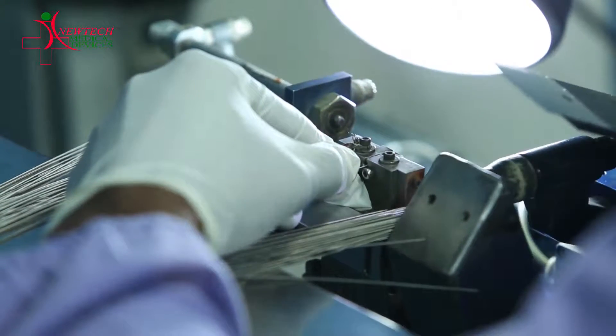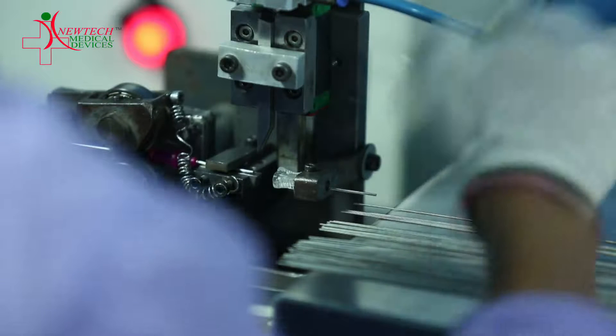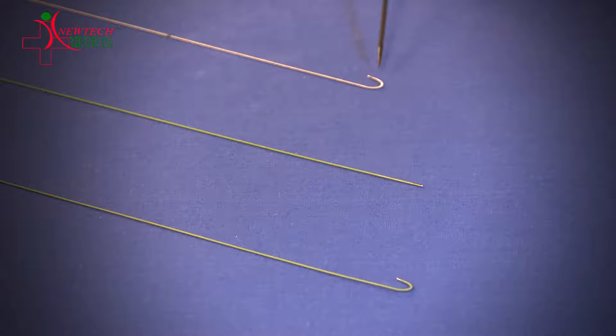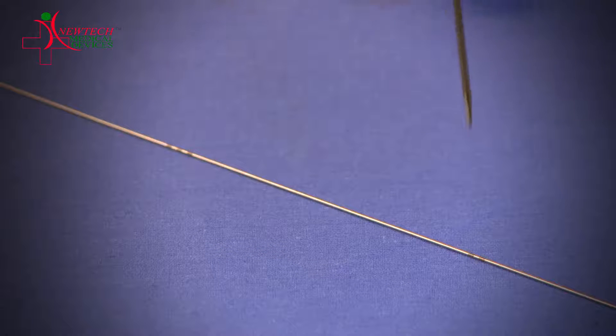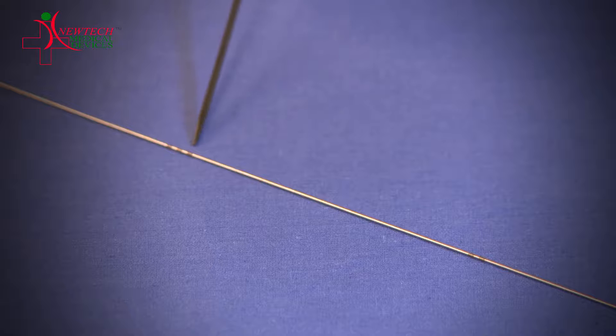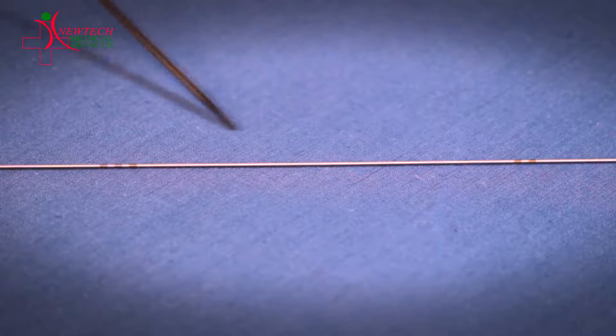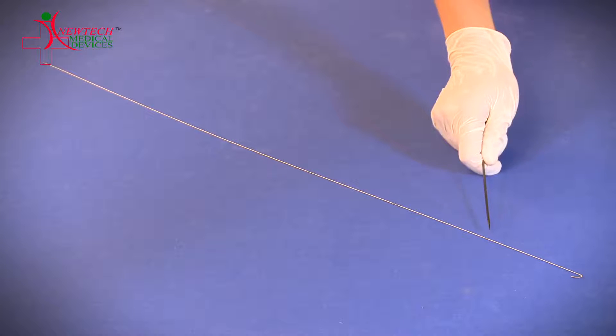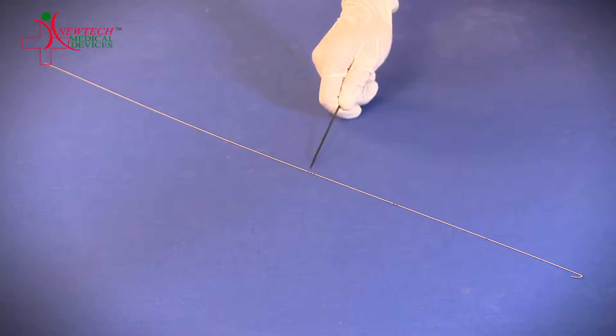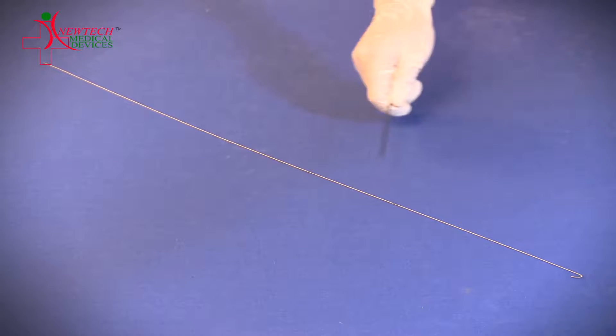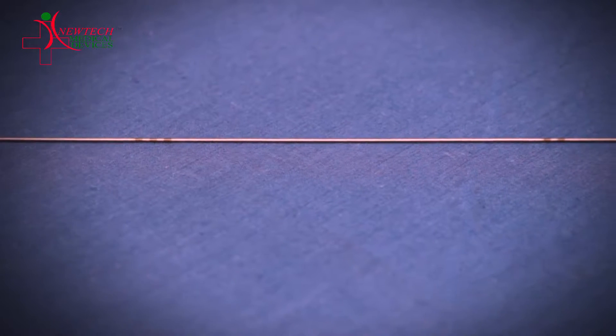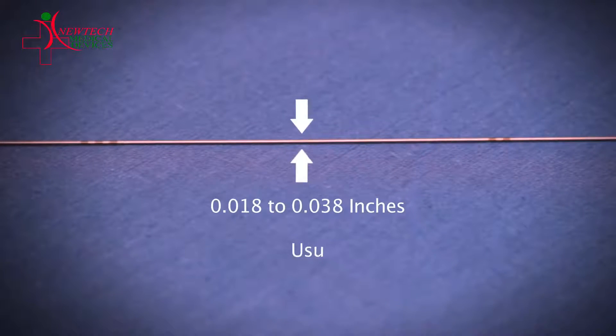New Tech Medical is the only company in India that manufactures guide wires. We can manufacture J-tip or straight-tip guide wires, coated and uncoated. In the uncoated guide wire, we provide centimeter markings at a distance of 10 centimeters. Its core can be made up of stainless steel or nitinol. Using the centimeter marking at every 10 centimeters, the doctor can understand what portion of the guide wire is inserted into the body.